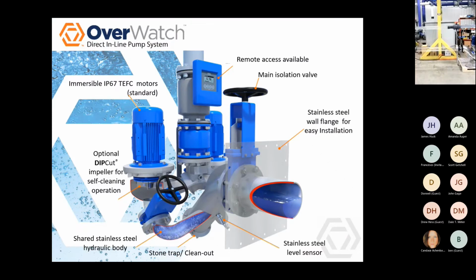So the system, as I mentioned, is 2 pumps on a common shared body. In this picture you see here, the inlet liquid or the influent is coming from the right-hand side through a wall plate. So if you're talking about a wall flange, we're using an existing basin where you have a pipe that sits back in the basin. We can provide your wall flange to bolt right up to that basin wall, and then you can mount the OverWatch right to that. Liquid flows down the swan neck. You're going to come to a liquid level transducer, and I'll point that out on the real system when we go turn on the camera and go live. That is our floats, right? What we're doing is we're measuring liquid pressure above that point at all times and setting parameters of how we want the system to operate based on that liquid elevation. So quite simply, low pressure off, high pressure on.